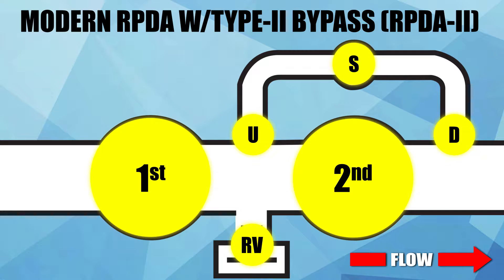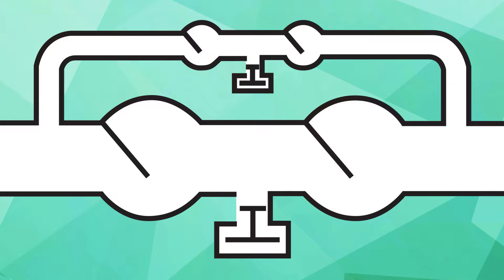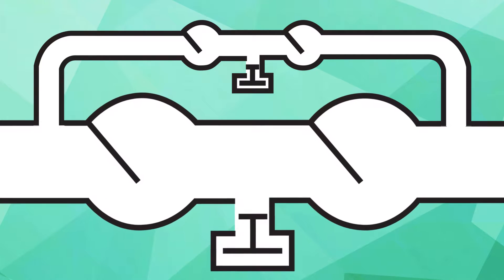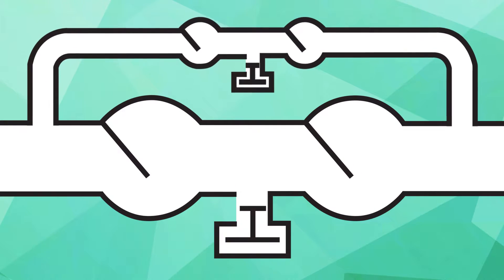Now that we have described the differences between the old RPDA Type 1 bypass and the modern RPDA Type 2 bypass, it is time to demonstrate how the two products provide exactly the same amount of backflow protection. When an RPDA of any type experiences a backflow condition, water can travel in reverse through two different paths: a path through the main valve or a path through the bypass.